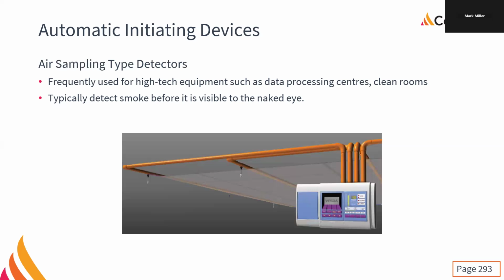And so instead of just getting them configured properly, they're just removing them. In the early days of air sampling detectors coming out on the market, special technicians would come in and do the configurations. Like VESDA trained technicians would come in and do the commissioning on these things and get them dialed in properly, and those things worked great. When they stopped doing that, it was just normal fire alarm technicians who might not have much or any specialized training on VESDAs, and they're just reading the instruction manual. I don't think it's sufficient, right? So there can be issues with it.